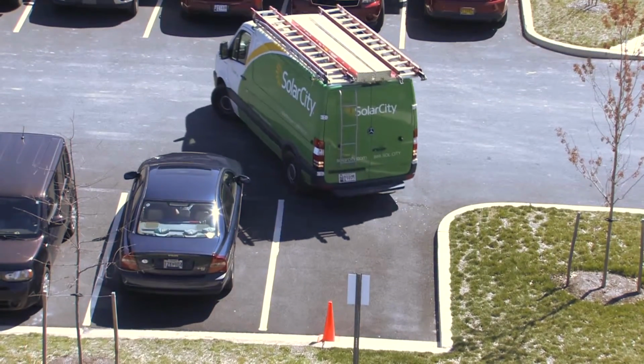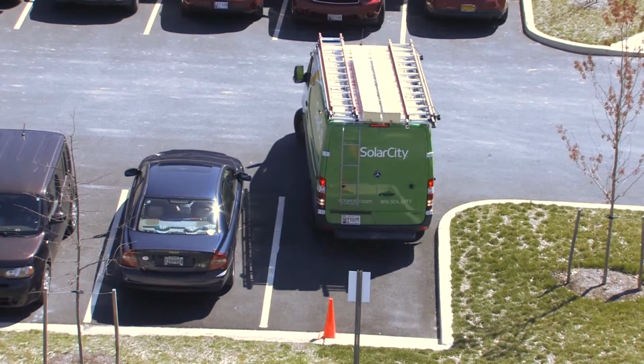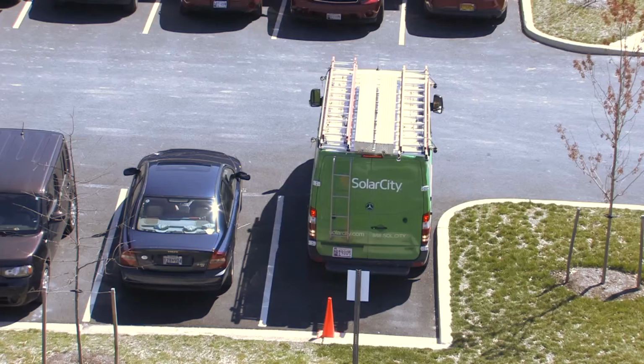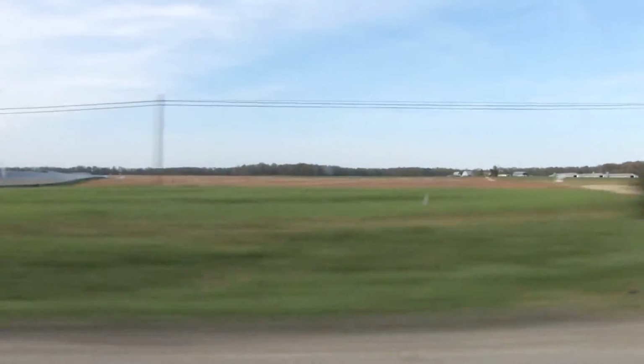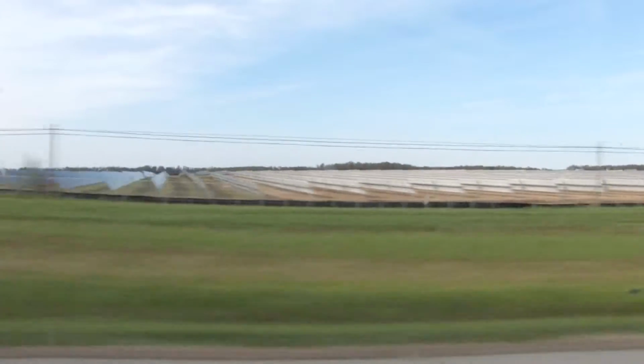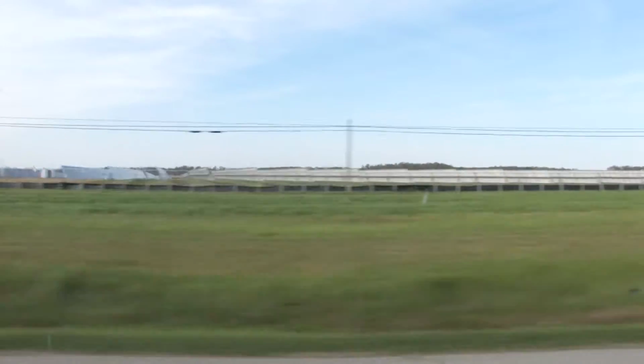When we went to apply for interconnection to the regional grid, we were told we weren't allowed to connect our solar project to the grid node in Y Mills. This is at least partly because there's a 90-acre, 13.7 megawatt project going in right around the corner from the college that connects at the same grid node. Simply put, our small project was going to overwhelm the grid node, particularly with regard to safety concerns at times of max productivity for the array.